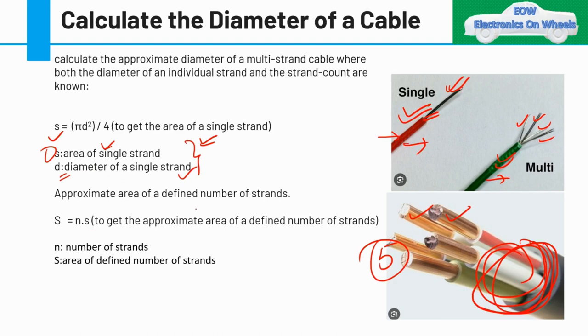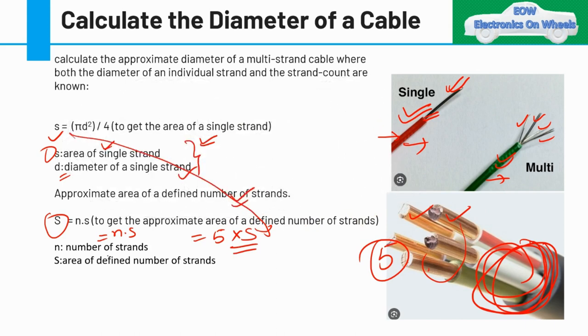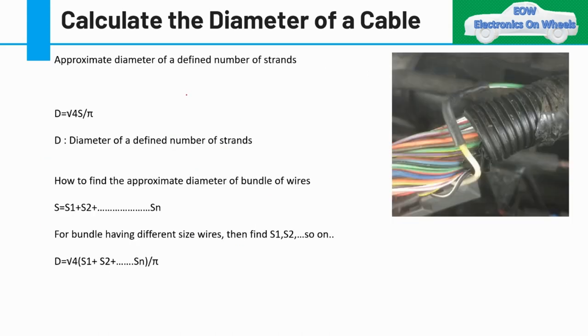Now if you have multiple strands, the approximate area of the bundle is n × s, where n is the number of strands and s is the area of a single strand. For example, if you have five strands, it's 5 × s. To find the diameter of the bundle, the formula is: D = √(4S / π), where S is the total area of the defined number of strands.